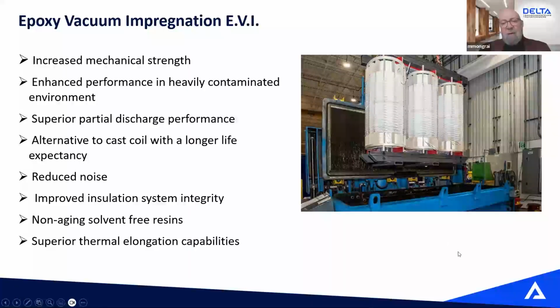And one of the best characteristics of epoxy is that once it's cured, the epoxy coating will remain flexible. A varnish is stiff as a piece of glass, same as polyester resin. By being flexible, when your transformer is sitting at idle, no load, it's probably going to go up to 100 degrees. But then you apply full load, or your inverter is pushing the maximum output at noon. So you go full load, the temperature of the transformer will go up, your winding will expand, your core will expand a little bit, and then at night it's going to cool down, it's going to contract. So the epoxy will have the capability of expanding and contracting with the fluctuation of load much better than a transformer coated with varnish or polyester resin. So that's why you won't see flakes or cracks in our coating after a few years, because it's flexible.